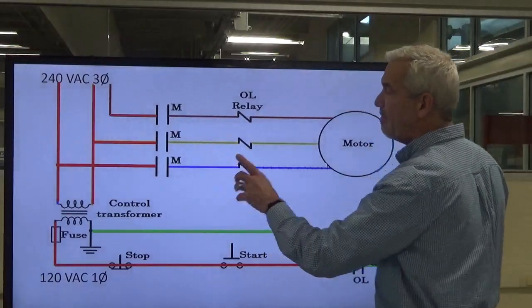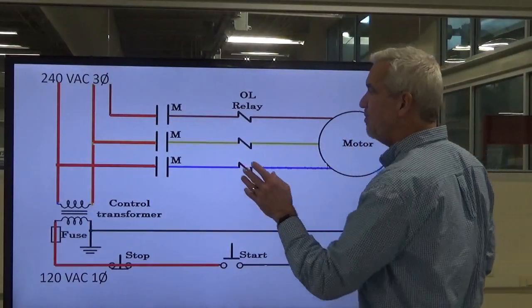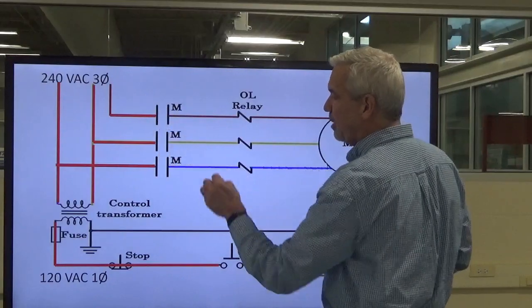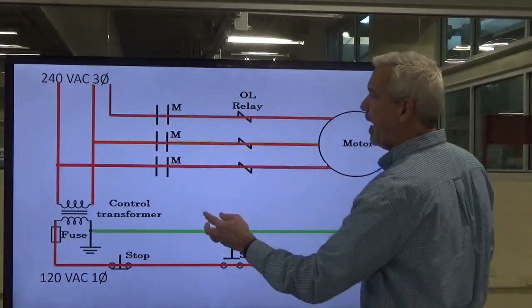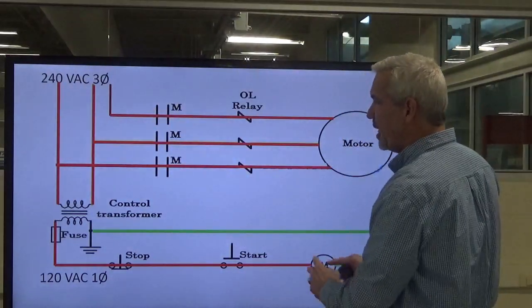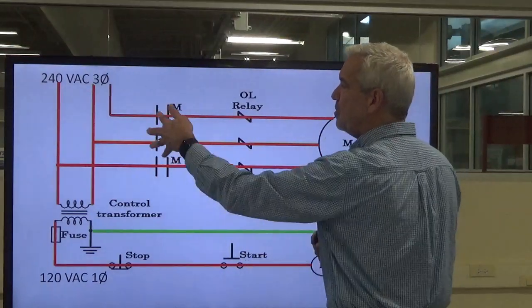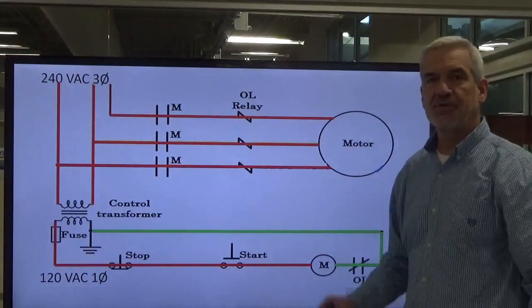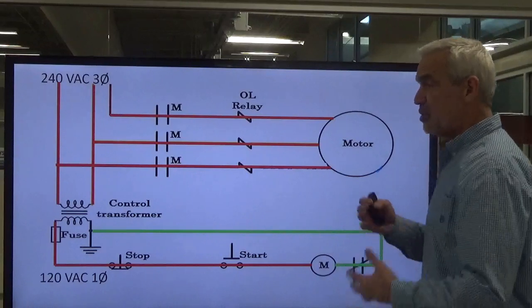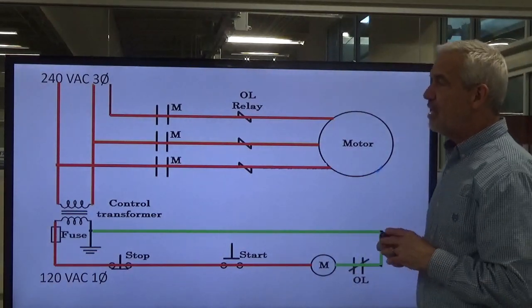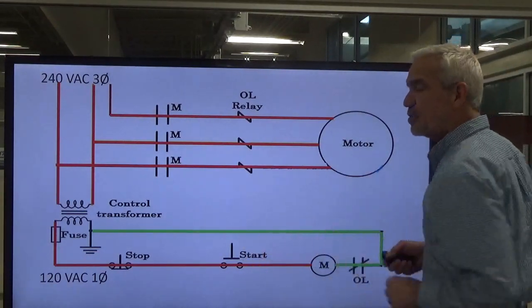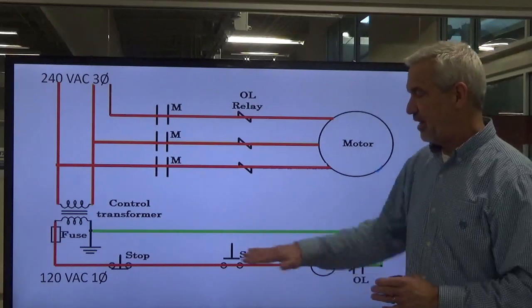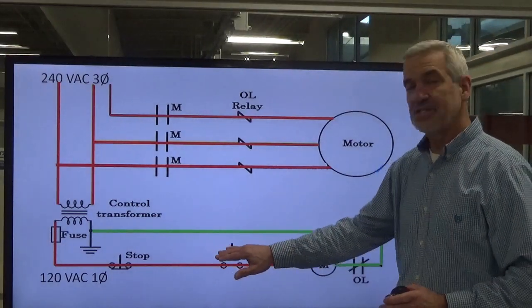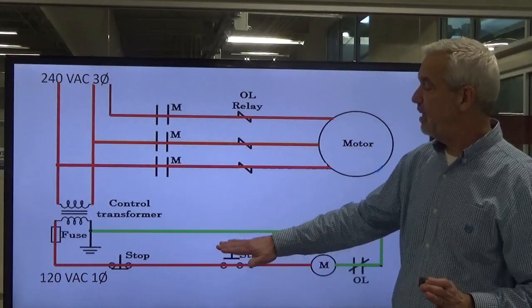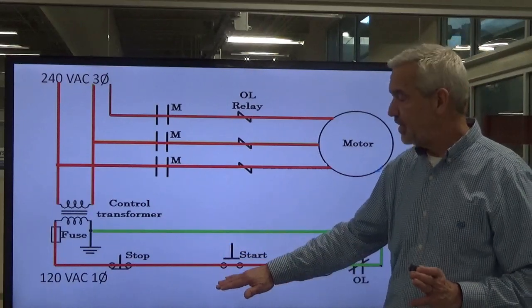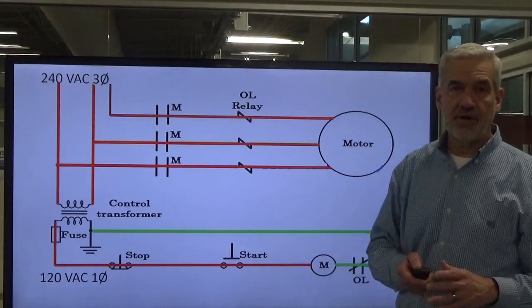Now, what's also happening at the exact same time, okay, is these contacts are going to close. So I'm going to run through this again, and when this energizes, it pulls these contacts closed, and now we have a path of three-phase voltage to our motor. Okay, so we're running along just as happy as clams because we are holding our start button in. If you'll simulate that again with me, our normally open is now closed. Not normally closed, but it's just considered closed. These contacts are closed, and we're allowing current to flow through here.